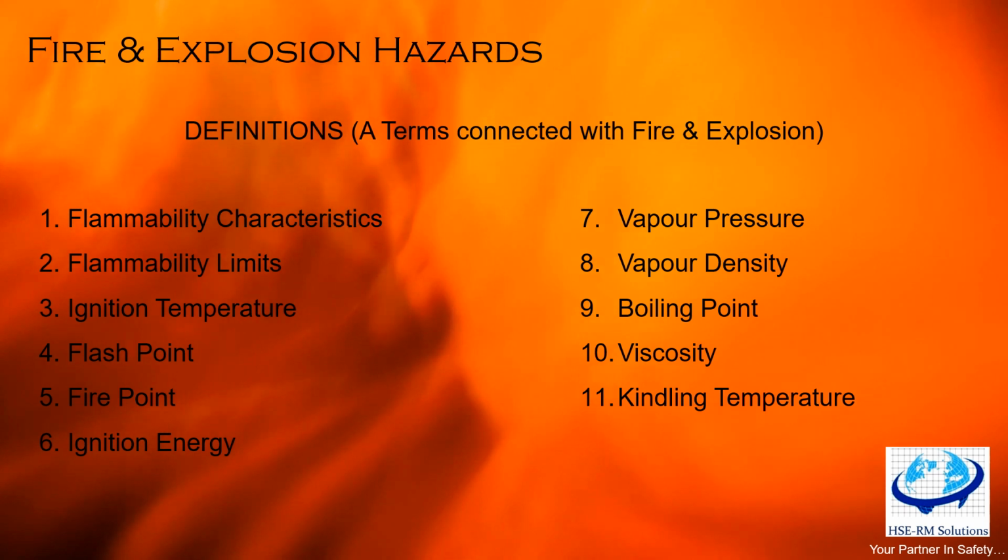So I'll again explain the UEL. When we explained the lower explosive limit, then above a certain concentration, when the concentration of gas increases, the upper flammability limit, it is too rich and is also called the upper explosive limit. The concentration between these limits constitutes the flammable range.